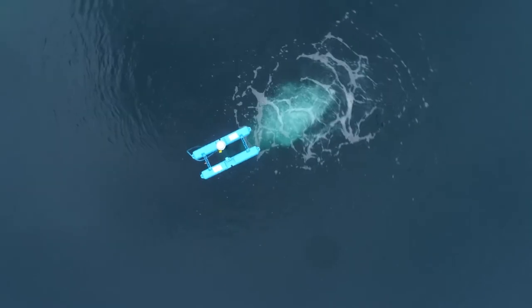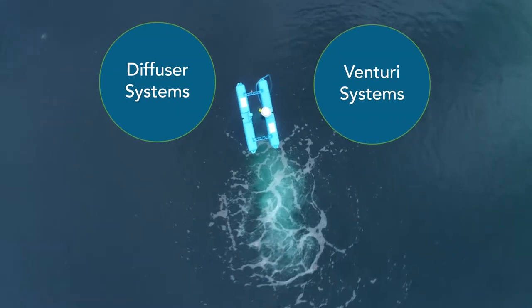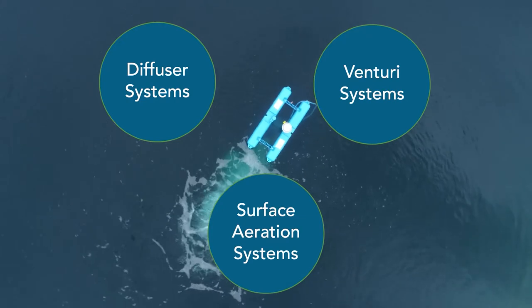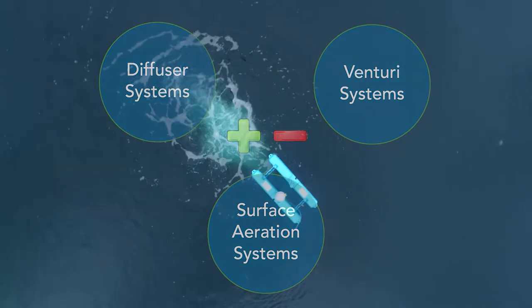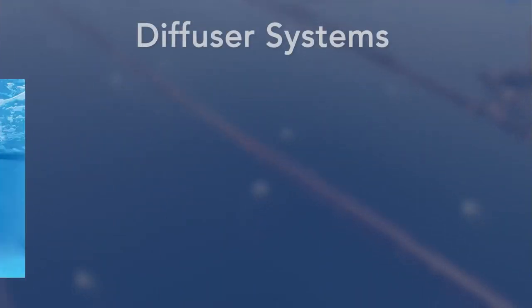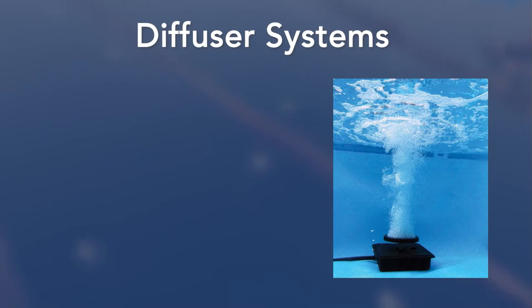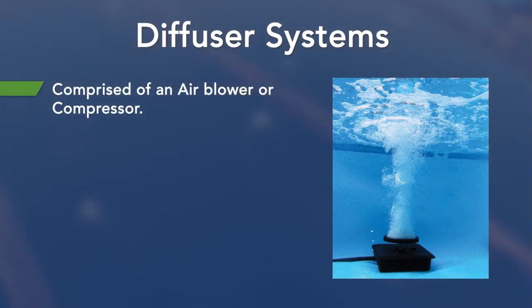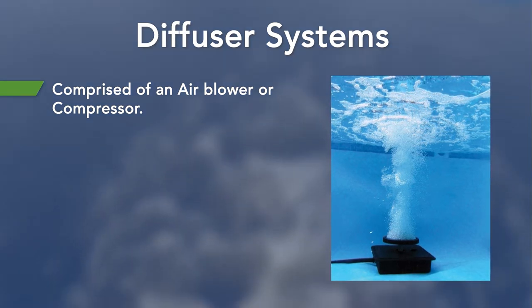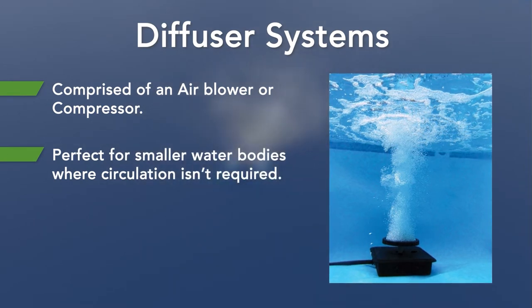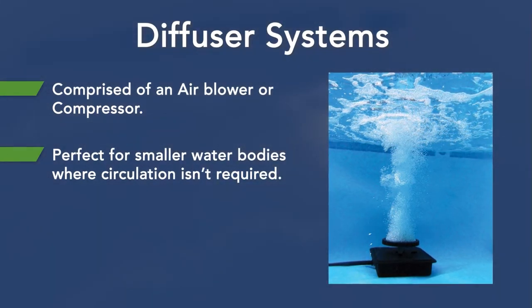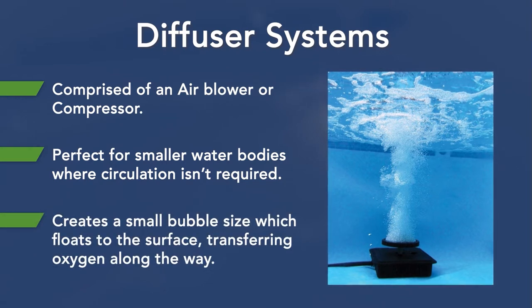There are many types of aeration devices, but the most common are diffusers, venturi systems, and surface aeration systems. Each of these systems has its own positive and negative aspects and suits different applications better than others. So let's take a walk through it all together. Diffuser aeration systems generally comprise an air blower or compressor with a hose running out to a diffuser station. Diffusers are an effective way to introduce oxygen in small-scale water bodies where very little circulation is required. These systems create a small bubble size which floats to the surface, transferring oxygen through the water along the way.